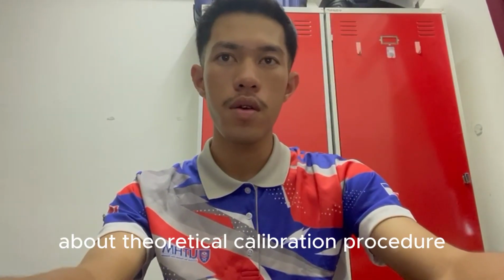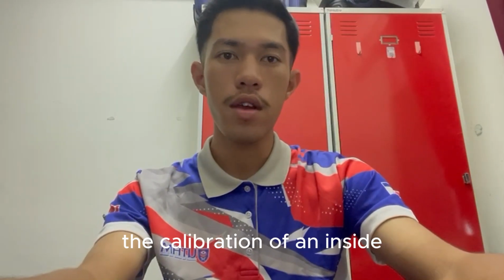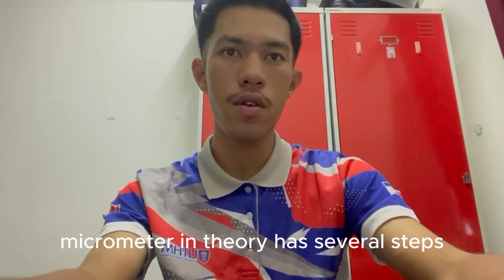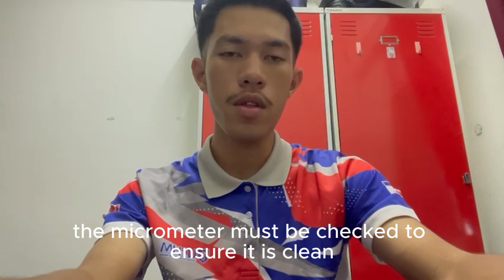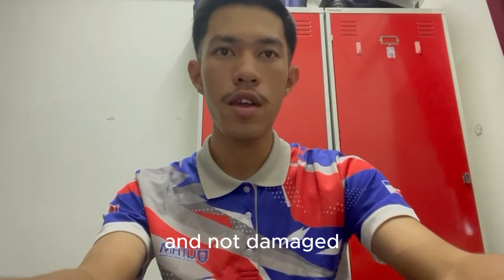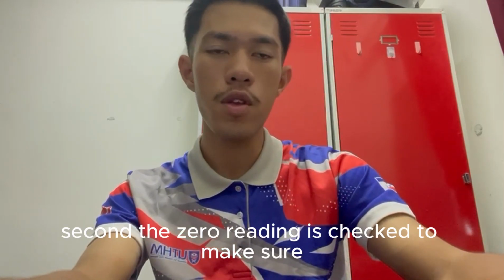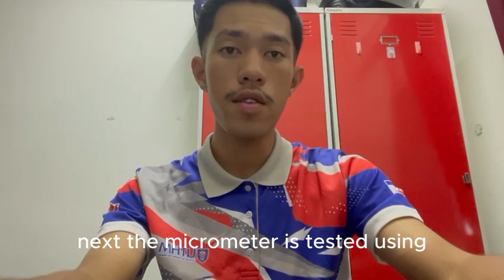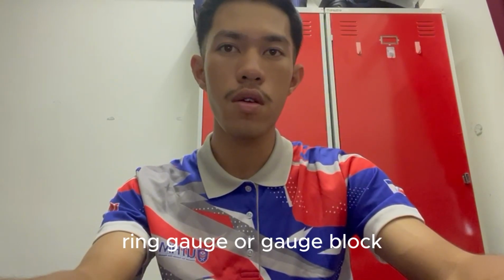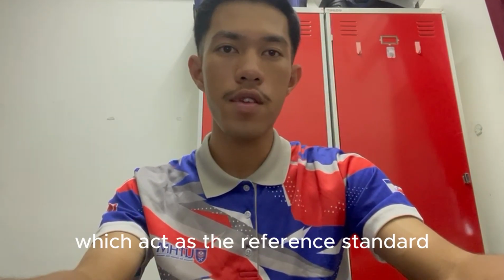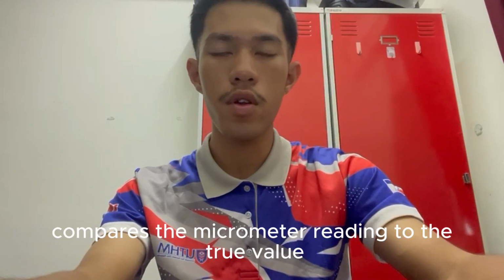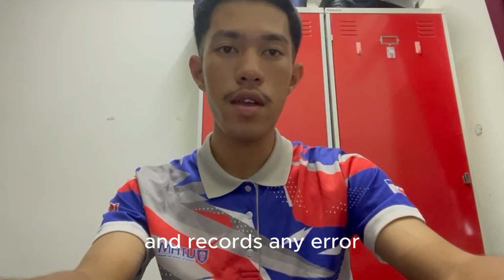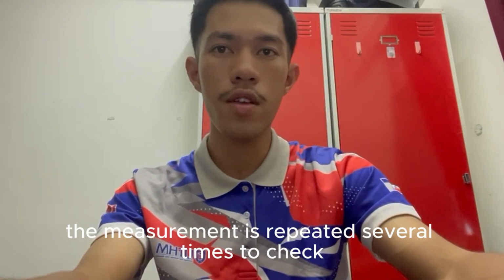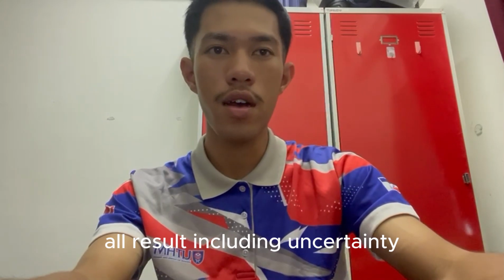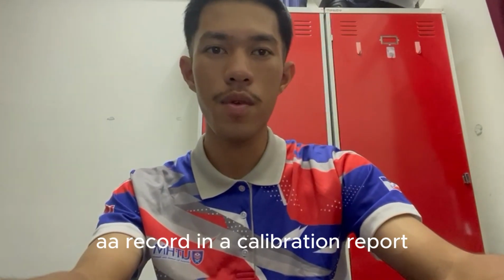Number 4 is about the theoretical calibration procedure. The calibration of an inside micrometer in theory has several steps. First, the micrometer must be checked to ensure it is clean and not damaged. Second, the zero reading is checked to make sure the scale starts correctly. Next, the micrometer is tested using a ring gauge or gauge block, which act as the reference standard. The user compares the micrometer reading to the true value and records any error. The measurement is repeated several times to check consistency. Finally, all results including uncertainty are recorded in a calibration report.